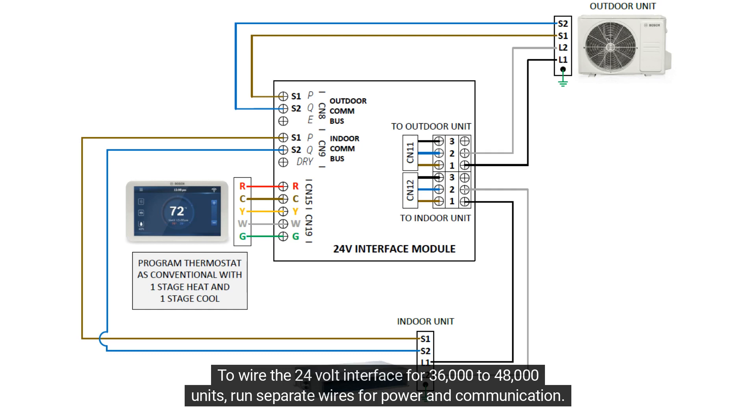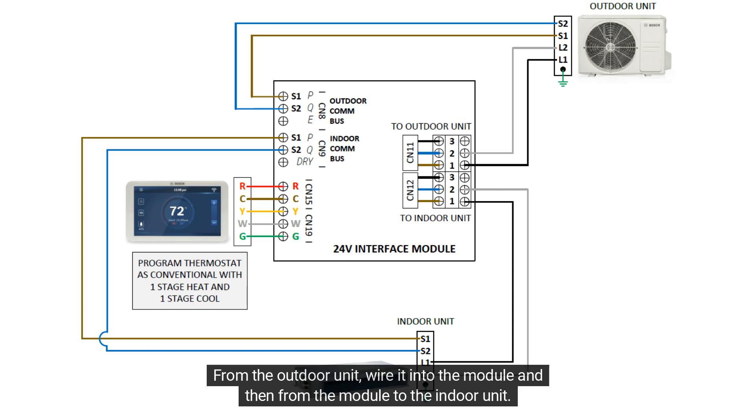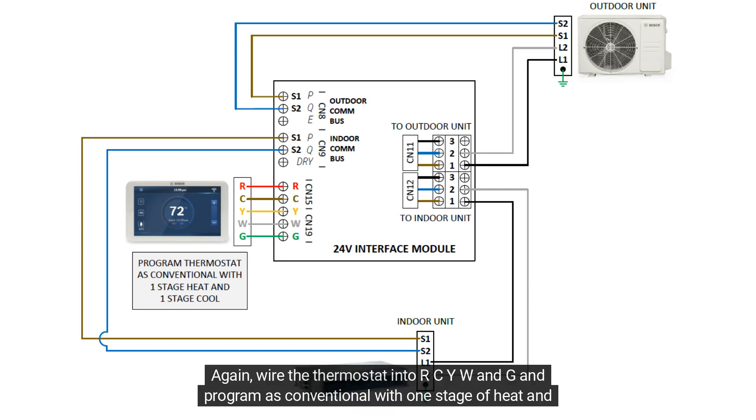To wire the 24-volt interface for 36,000 to 48,000 units, run separate wires for power and communication. Your power wire will connect at L1 and L2 — from the outdoor unit, wire it into the module and then from the module to the indoor unit. Your communication wire will connect to S1 and S2 — from the outdoor unit, wire S1 and S2 to the outdoor comm bus on the interface and from the indoor comm bus to the indoor unit. Wire the thermostat into R-C-Y-W-G and program as conventional with one stage of heat and cool.